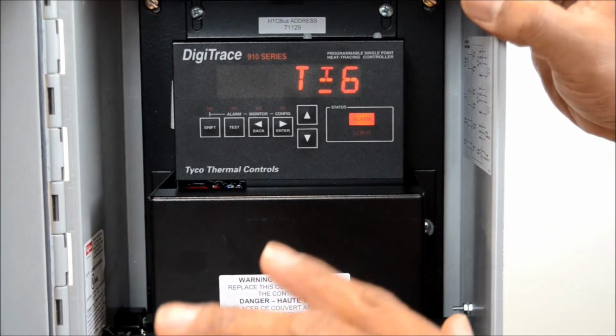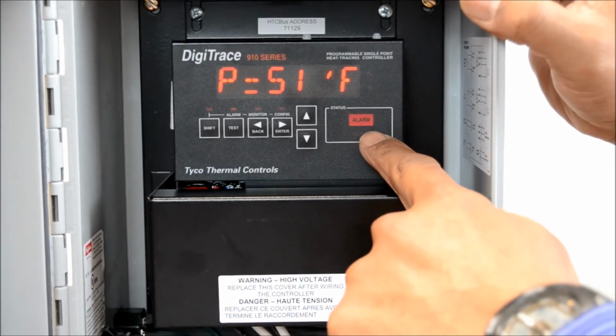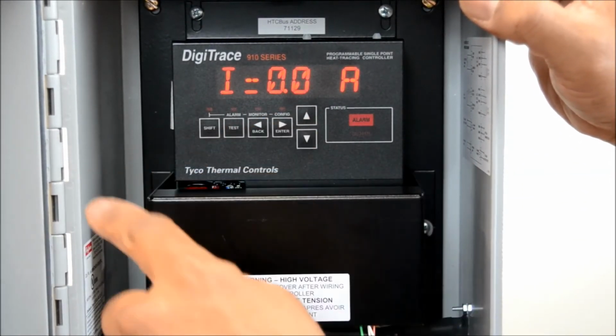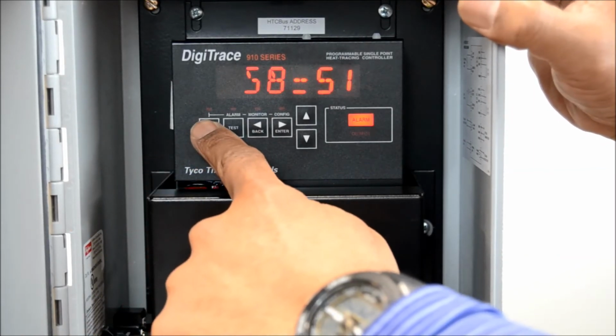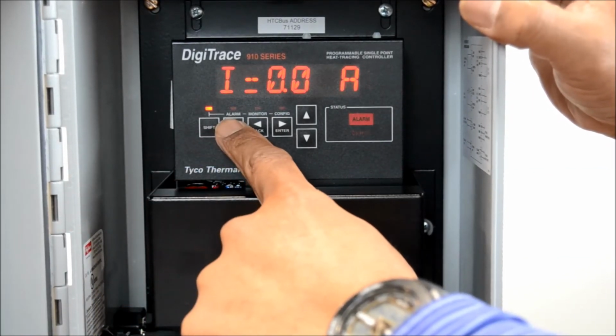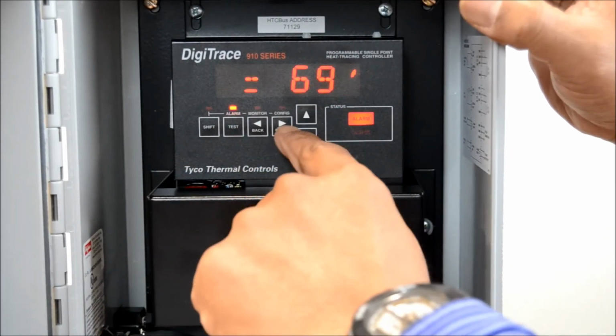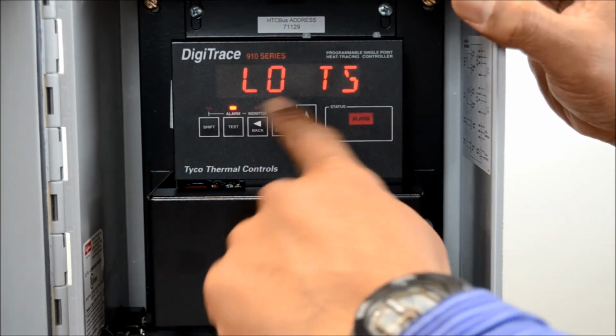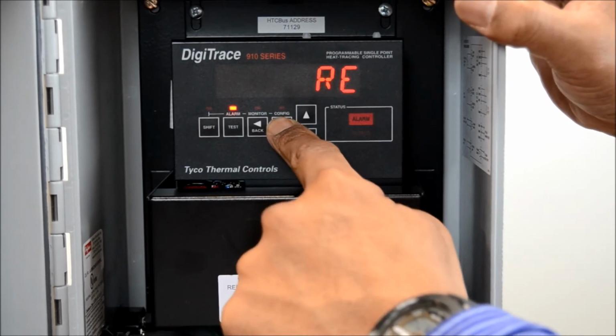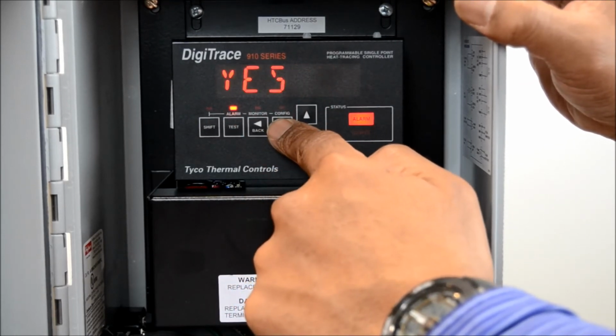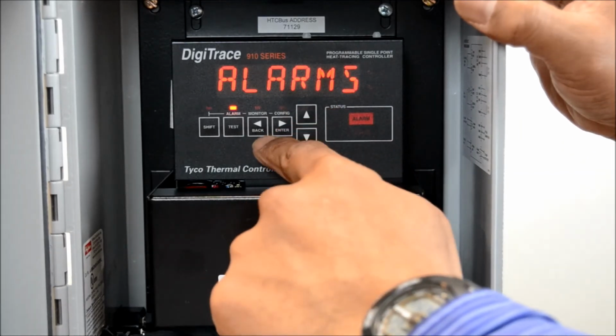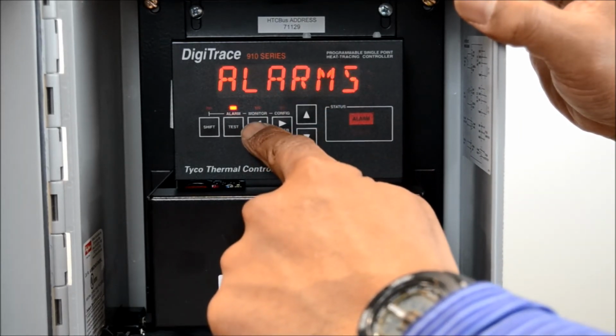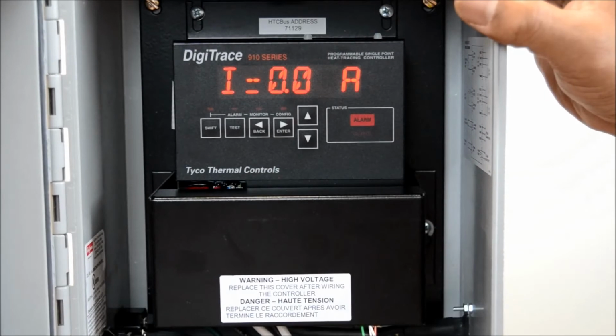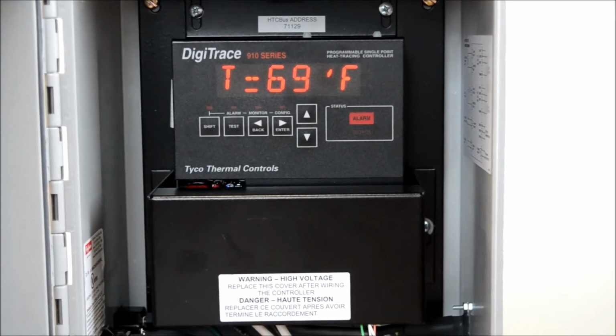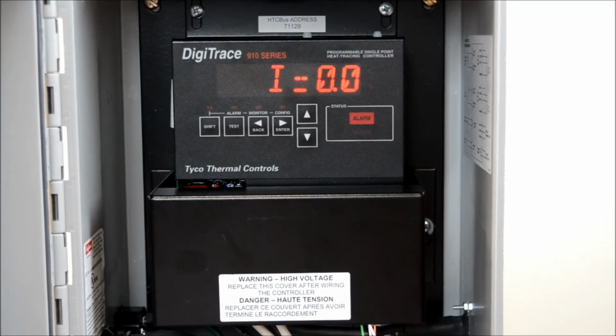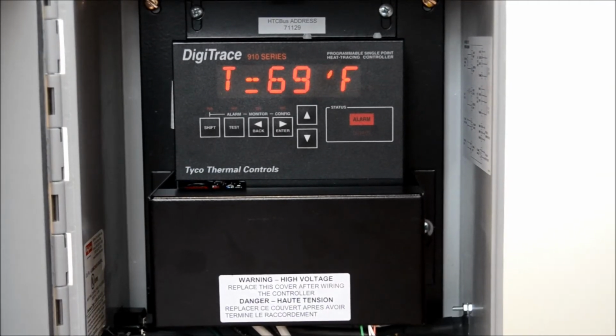Right now I'm out of the system as far as programming. The alarm is still flashing. The reason why is because now I have to go into the alarm menu and clear it. So you hit shift, alarm, and then you have this reading, low temperature. You're going to hit enter and it's going to ask you to reset. It says yes, no alarms. It reads now. Now I can back out of the system and it's all cleared and ready to go again. So anytime you have an alarm, like I said before, you're going to have to clear it first.